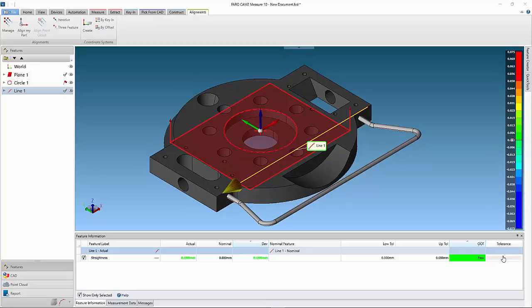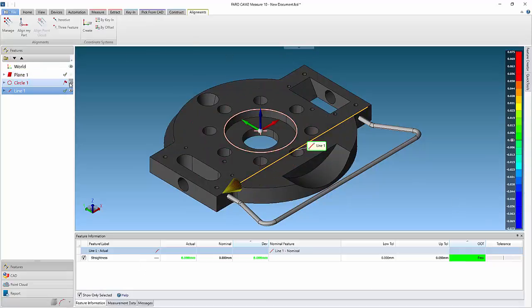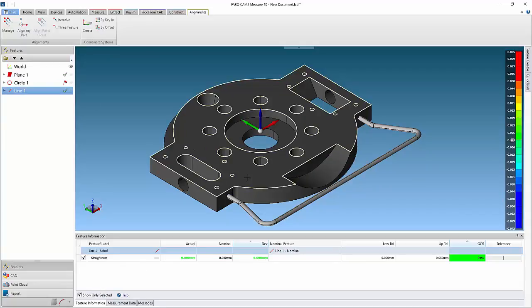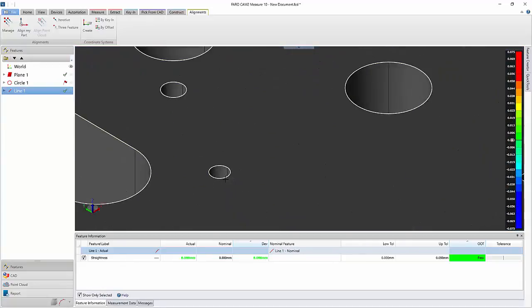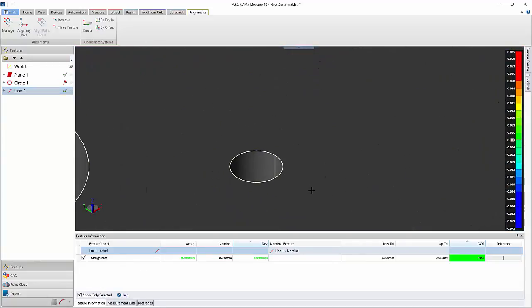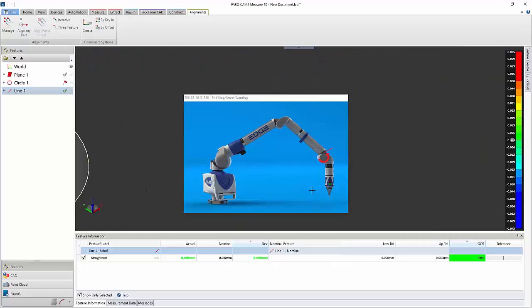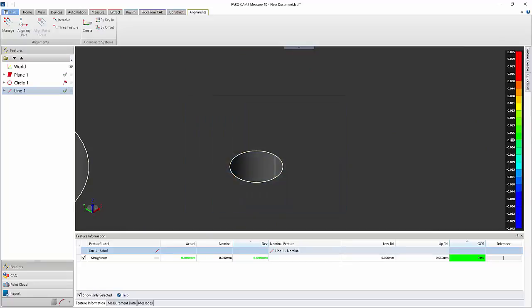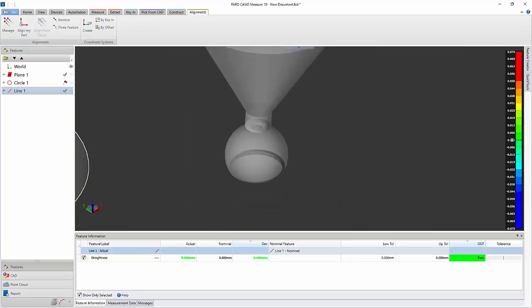Magnetic cones or holes which have a smaller diameter than the probe can be used to measure the reference points. In this case, we are using small machined holes to locate the probe and measure the reference points.